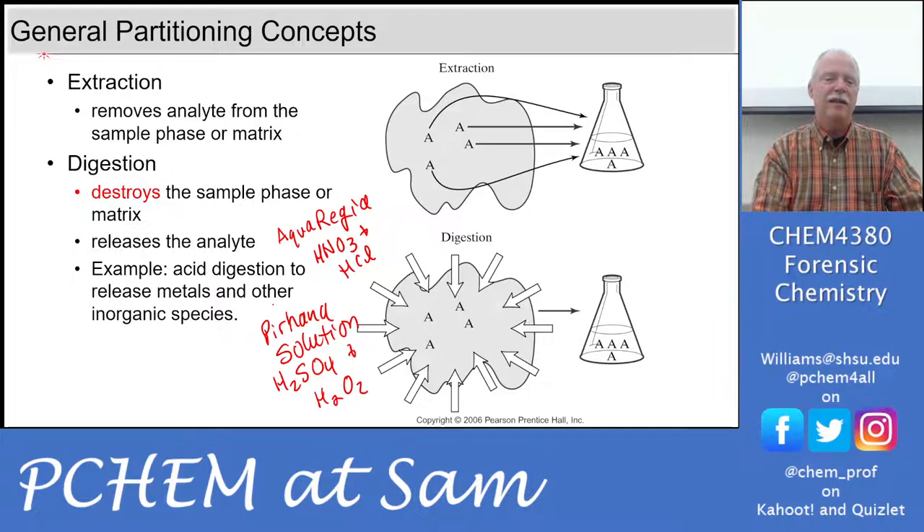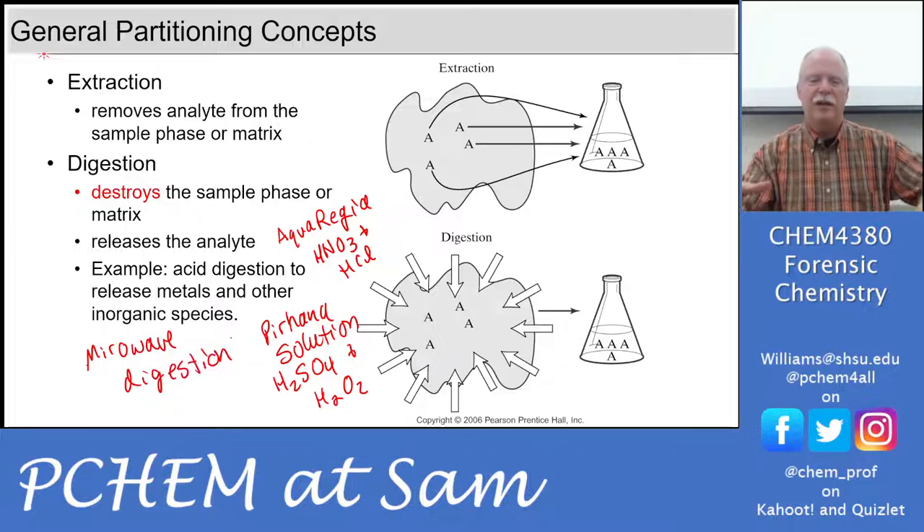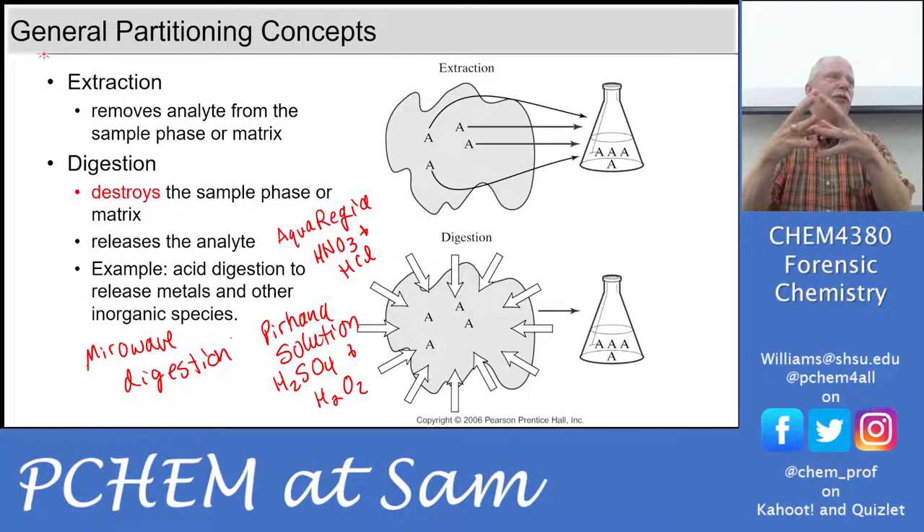You can also add heat to these. A lot of times they have special microwave ovens made for microwave digestion — a kind of industrial-power microwave oven that comes with really thick Teflon bottles. You put your material in there, put in your acid, and then put it in the microwave. The microwaves go through the Teflon and heat up the liquid inside. They have a little vent on top, but you can really get hurt with microwave digestion because it can superheat the liquid.